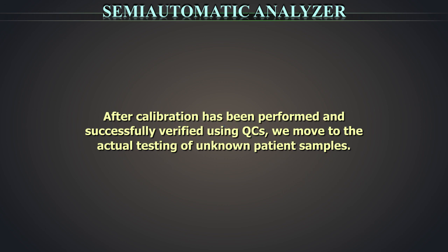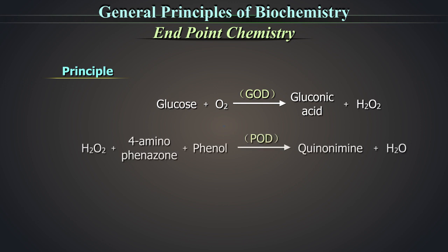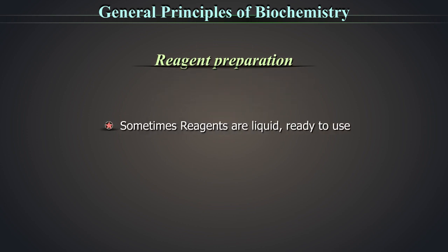After calibration has been performed and successfully verified using QCs, we move to the actual testing of unknown patient samples. Glucose is oxidized into a red-colored compound. The intensity of the red-colored compound is proportional to the glucose concentration and is measured at 505 nm, which is 490 to 530 nm. Regarding reagent preparation: sometimes reagents are liquids, ready to use.